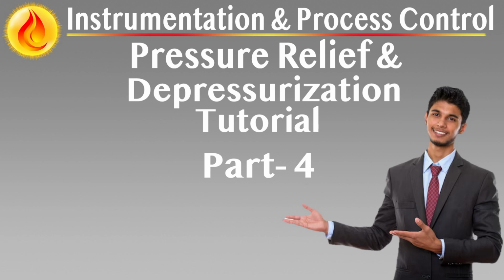Key functional requirements. Stable combustion must be maintained in all weather and flaring conditions, including high wind speeds, varying gas flows, and intermittent flare usage. Multiple pilots are required to ensure redundancy and complete flame coverage. For flare tips up to 400 millimeters diameter, at least 2 pilots. For flare tips larger than 400 millimeters, at least 3 pilots. Each pilot must be fitted with a dedicated ignition line to allow individual startup and reignition.